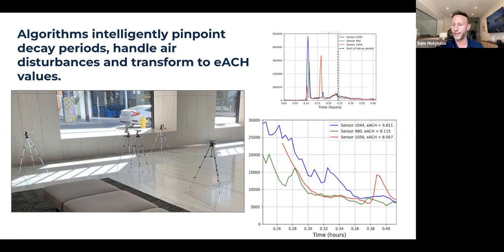The other thing we see is people walk by, and there are disturbances in the air that need to be accommodated and adjusted for. Otherwise you have to repeat these measurements, which can be warranted to get reproducibility. But we've designed algorithms that can handle the noise and are robust to fluctuations in the environment, to reach that consensus or final equivalent air change rate for the space.